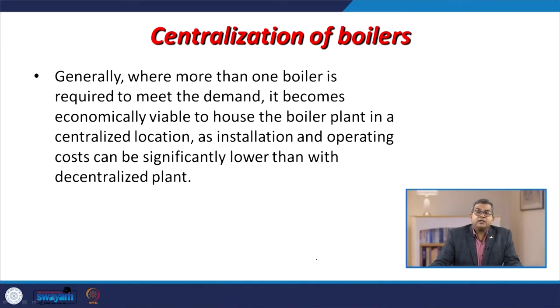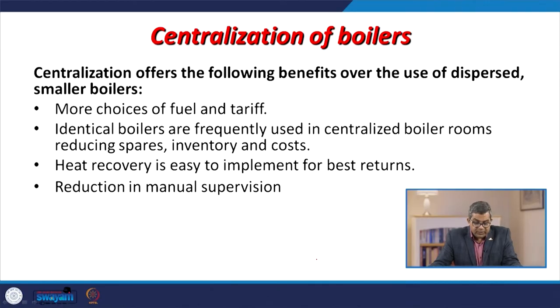Generally, when we are talking about the centralization of a boiler, when more than one boiler is required to meet the demand, it becomes economically viable to house the boiler plant in a centralized location, as installation and operating cost can be significantly lower than with the decentralized plant. Centralization offers various benefits over the use of dispersed smaller boilers, that is, more choices of fuel and tariff. Identical boilers are frequently used in centralized boiler rooms, reducing the inventory cost, the spare cost and other things. Heat recovery is quite easy to implement for the best return, and there is also a reduction in manual supervision.